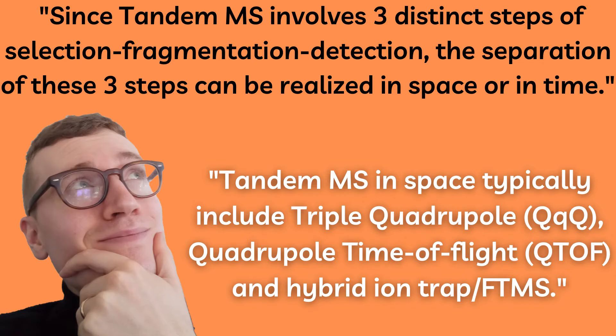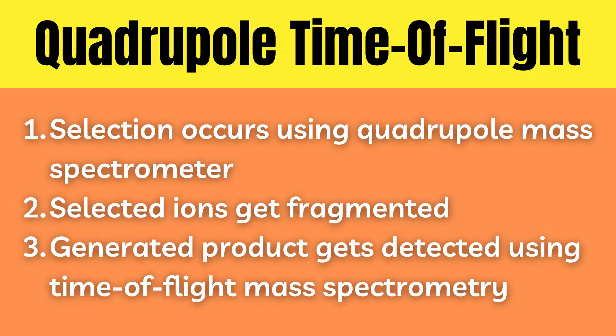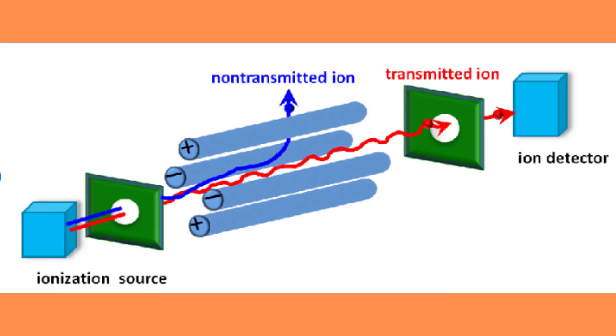We'll use quadrupole time of flight, or QTOF, as an example. In QTOF, precursor ions are selected with the help of the quadrupole mass spectrometer and sent to the collision cell for fragmentation. In other words, the first quadrupole Q1 operates as a mass filter, allowing only specific selection of ions based on their mass to charge ratio.